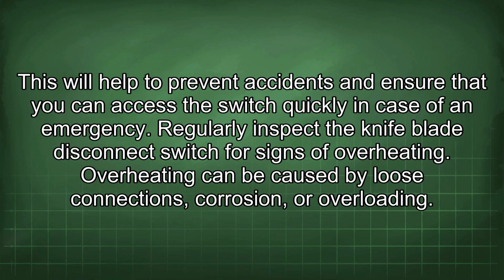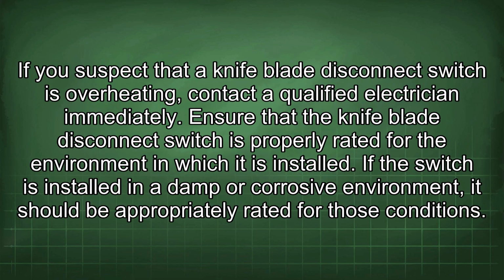Regularly inspect the knife blade disconnect switch for signs of overheating. Overheating can be caused by loose connections, corrosion, or overloading. If you suspect that a knife blade disconnect switch is overheating, contact a qualified electrician immediately. Ensure that the knife blade disconnect switch is properly rated for the environment in which it is installed. If the switch is installed in a damp or corrosive environment, it should be appropriately rated for those conditions.